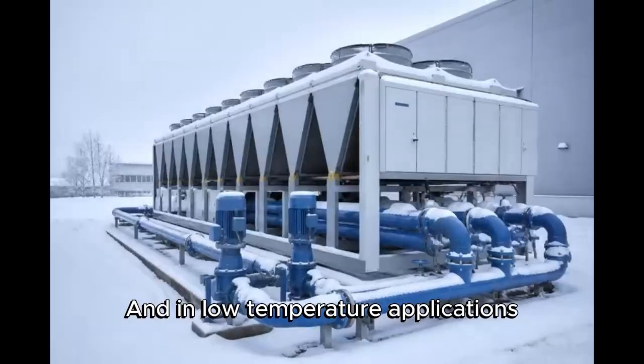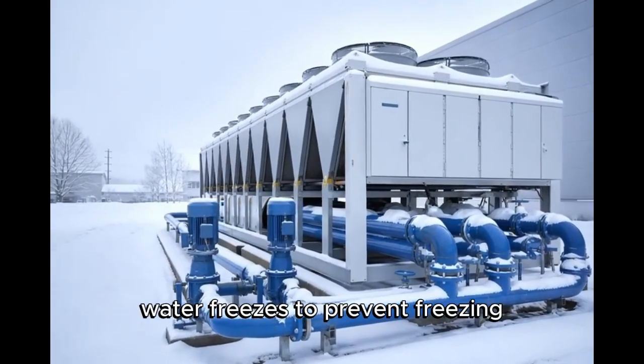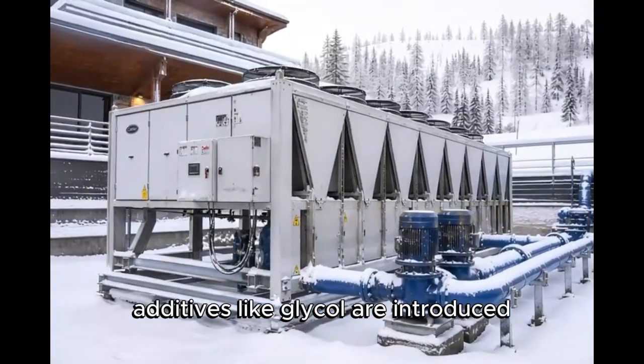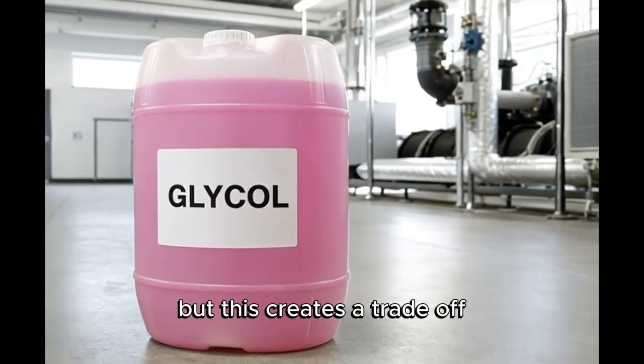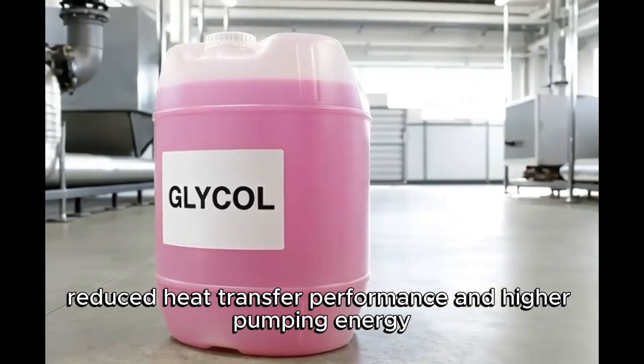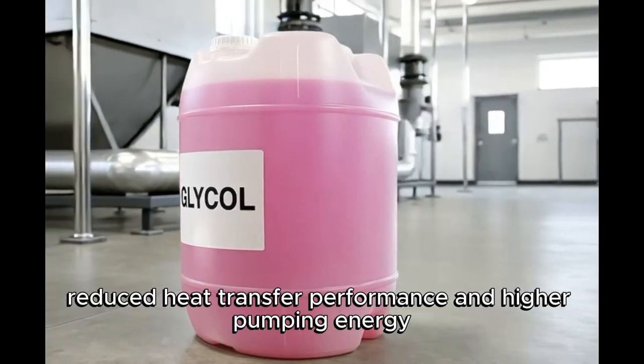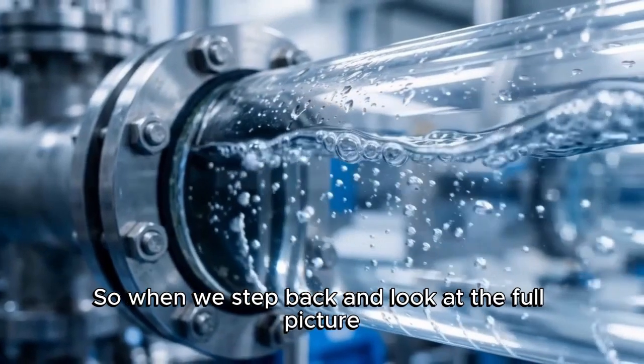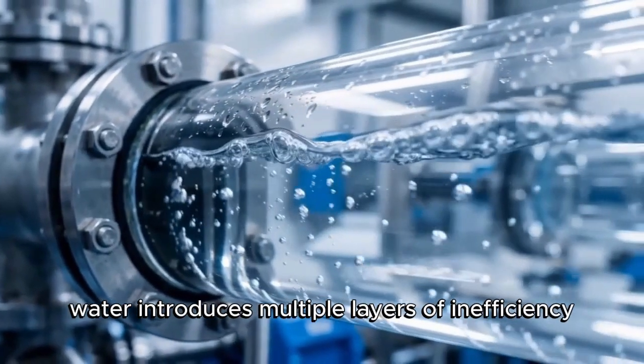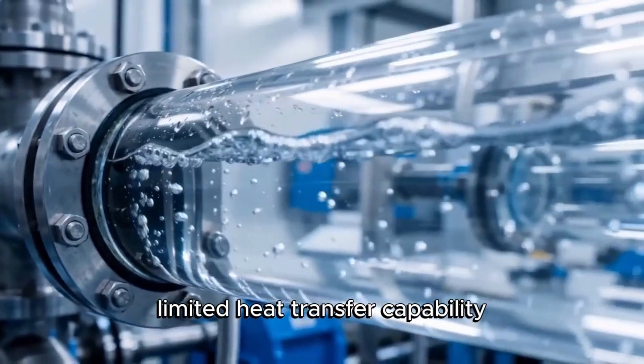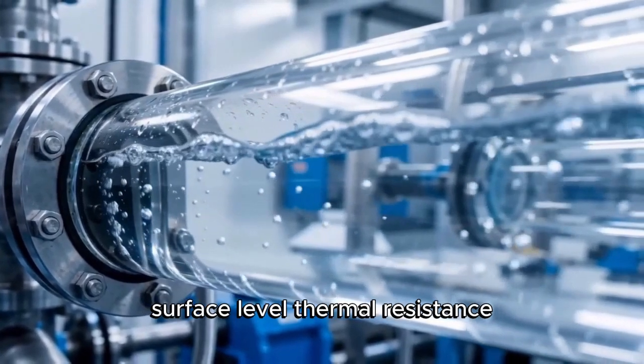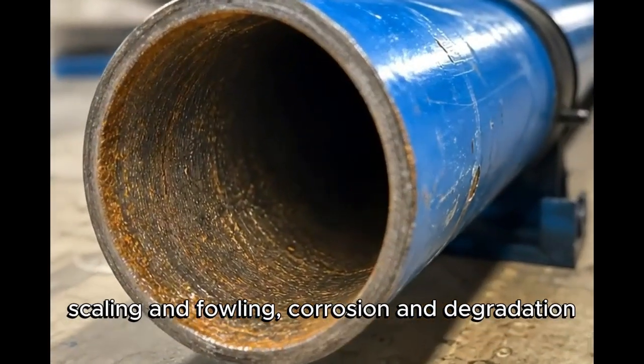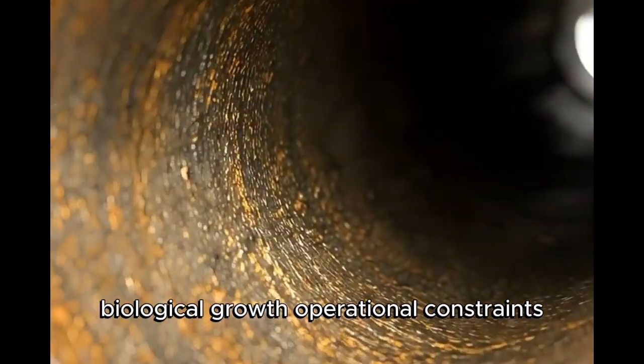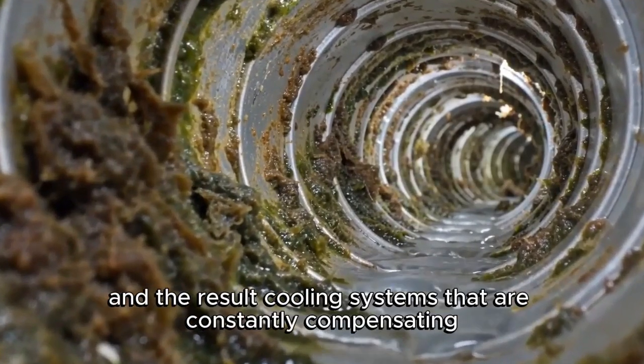And in low-temperature applications, water freezes. To prevent freezing, additives like glycol are introduced. But this creates a trade-off: reduced heat transfer performance and higher pumping energy. So when we step back and look at the full picture, water introduces multiple layers of inefficiency: limited heat transfer, thermal resistance, scaling and fouling, corrosion and degradation, biological growth, operational constraints, and the result?